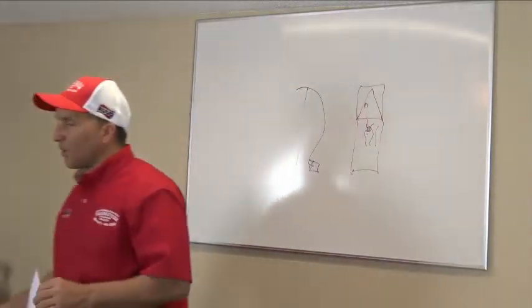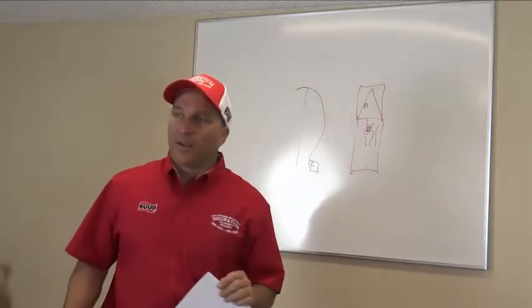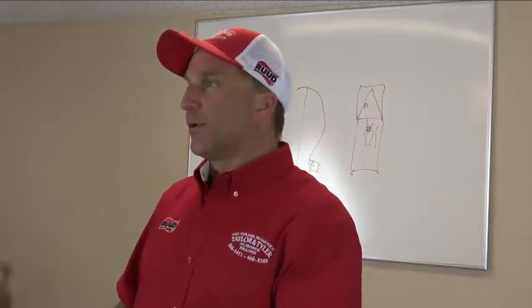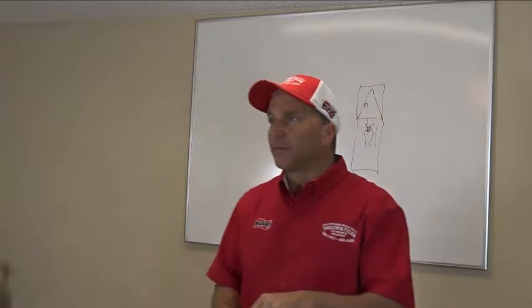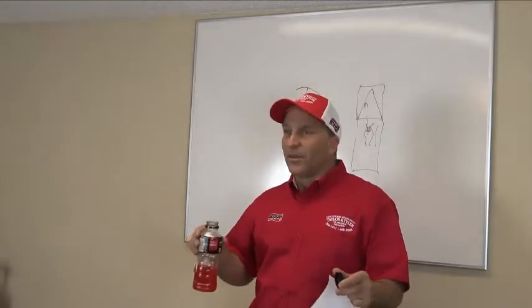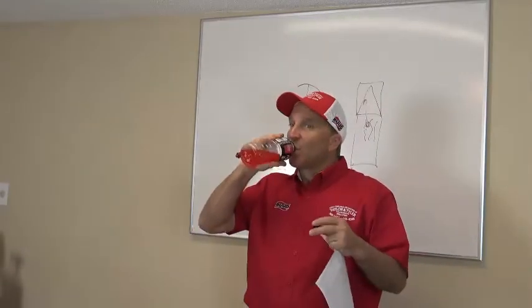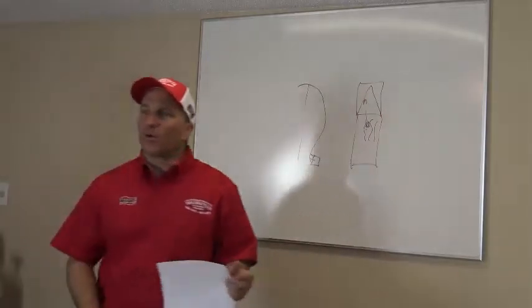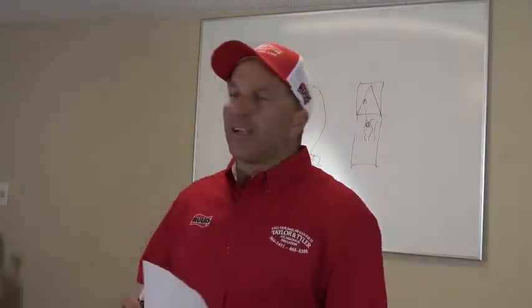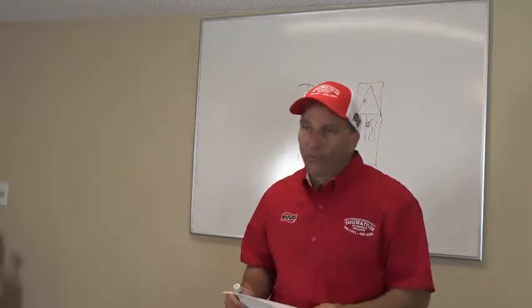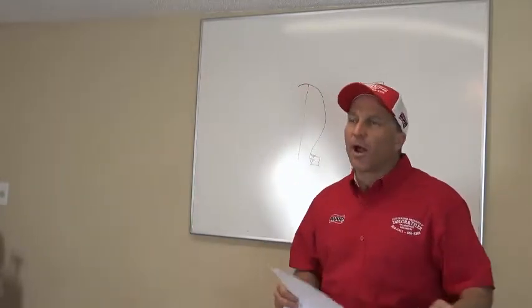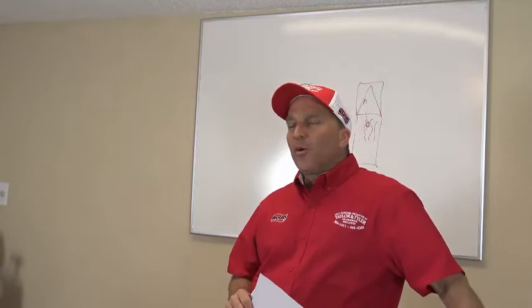Now, a leak search can run anywhere from $90, meaning labor to run a leak detector around the system, okay, to $550 to do a pressure test on the system. System's really low on refrigerant, don't you need to find out where the leak is at? Yes, sir. Did you find and fix the problem? Or did you make a recommendation?